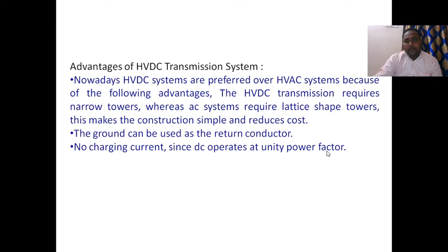Due to less corona and radio interference, it results in an economic choice of the conductor. The corona loss is less because the frequency is absent in DC. Whenever the corona loss is less, the radio interference is also less. There is no charging current in DC. Charging current Ic is fully based on frequency. Ic is V phase by Xc, that is 2 pi f C V phase. Whenever the frequency is 0, the charging current is also 0.